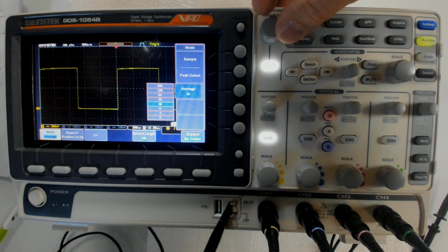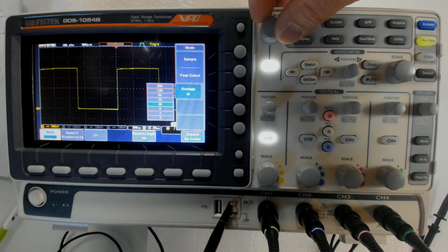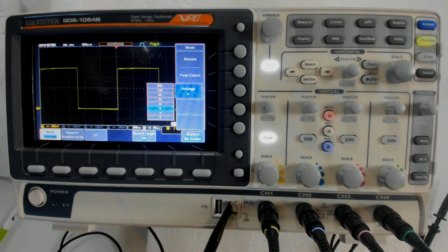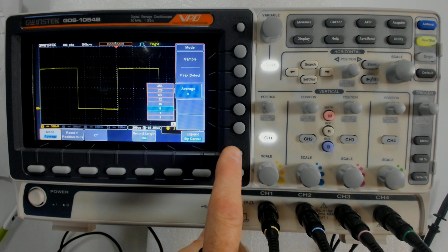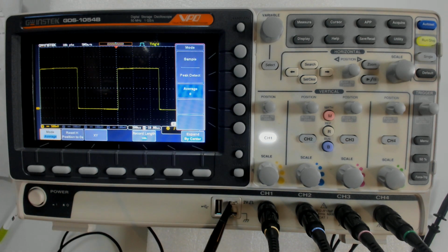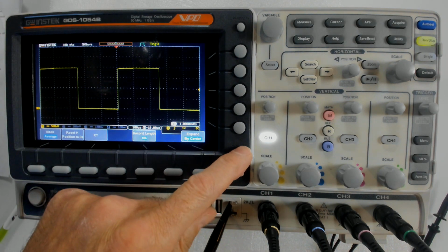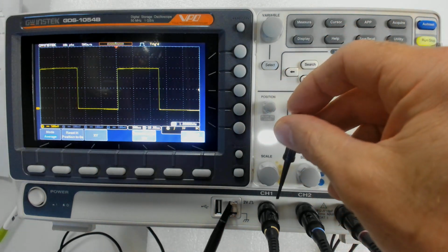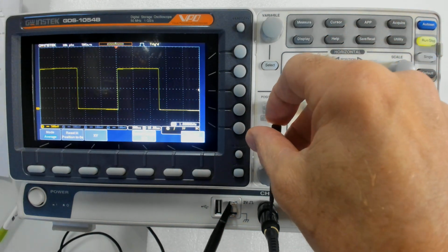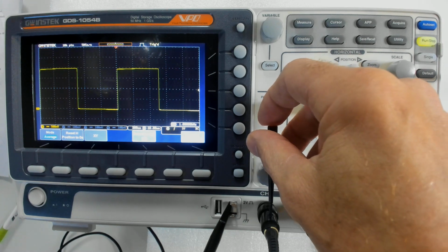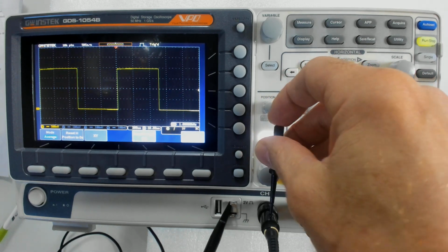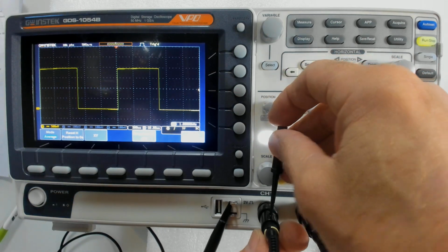Going to take 16 readings now and then average them and display that result. I'll go with 8, and it did give me a nice thin line to work with, which I like for my probe compensation, although it seems like we did pretty good even without magnifying it and doing the acquiring, the averaging. Let me get this off of here. But now you can see if I was going to fine tune it, if I wasn't happy with it, it looks pretty good. But look, my adjustment now for my probe should be a little more, I could make it even more precise. Let's see if I can get that.